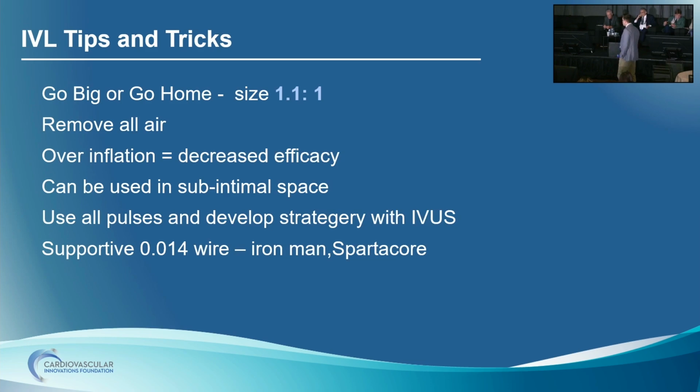The other thing is you don't want to overinflate this balloon when you're treating, okay? Because if you overinflate the balloon, it's a compliant balloon. You are stretching out the vessel further, which takes the emitters further from the calcium, okay? So then the sound waves have to travel further, and they're not as effective then. So the whole goal of this, you can shockwave at 1, 2, 3, 4 atmospheres. Nominal pressure is 6 atmospheres on these balloons, but you don't want to shockwave at 6 because it pushes the emitters further away from the vessel wall surface, okay?